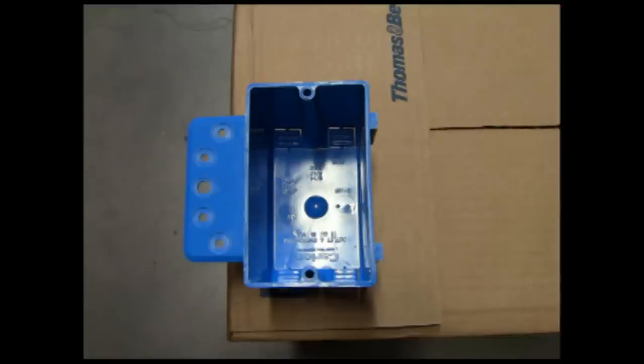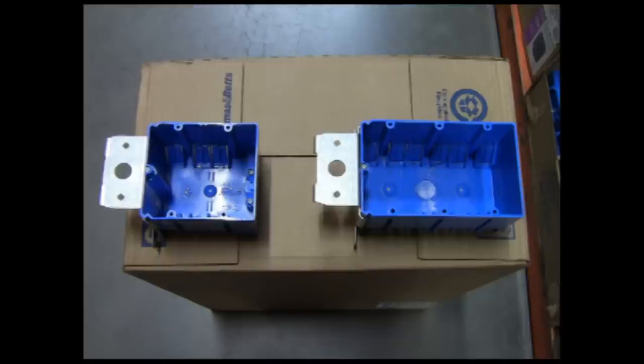Here's a box that is really handy. It is adjustable in depth. These boxes are excellent if you're not sure how thick the drywall is going to be or for outlets mounted behind cabinets that will need to be adjusted outward at a later time. They are also excellent for recording studios where sound abatement may be as much as 2 inches thick. The little screw you see on the left-hand side of the box will bring the box out when turned counter-clockwise. They also come in single gang.